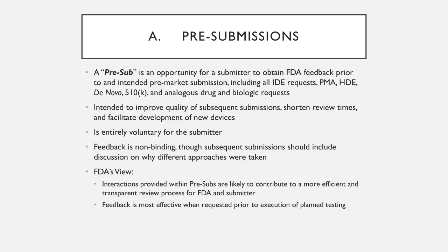The main purpose of these is to improve the quality of the documents being submitted to that ultimate submission. It's intended to shorten review time so that the regulatory bodies, the FDA, already have a good understanding of what to expect from some of these, and also to lessen their time with overly burdensome or unnecessary testing that might have been done and potentially not have been applicable or relevant to that particular submission process. And also, in order to shorten all those, it's to facilitate the development of new devices. A lot of companies were simply failing at that step because of the differences in expectations between the medical device companies and the regulatory bodies.